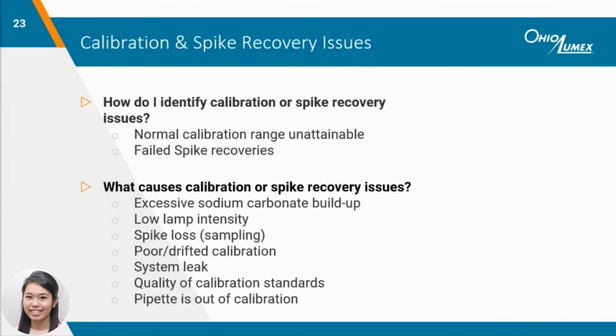A bad calibration will yield bad results. So calibration and spike recovery issues can sometimes go hand in hand. Having difficulty generating a linear calibration over your normal range or often failing spike recoveries is a sign that the analyzer may need maintenance performed. We'll delve into the root of the issues and discuss options to make calibration less difficult and yield better spike recoveries.